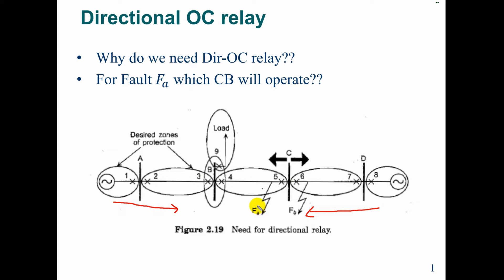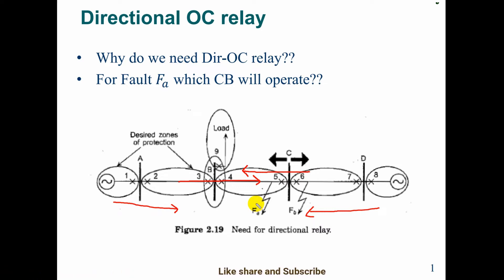Now for example, normal current is going in this direction — there is no fault. Normal current is going in this direction. And when the fault comes, the fault current direction changes. So we need a directional overcurrent relay. If the fault current direction is inverse or opposite to the load current, then we need to operate based on current direction.